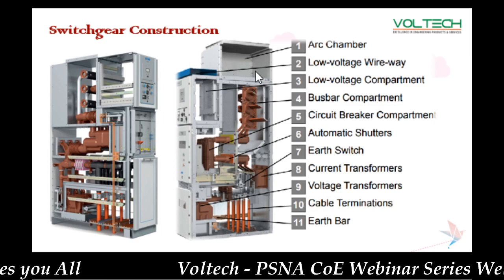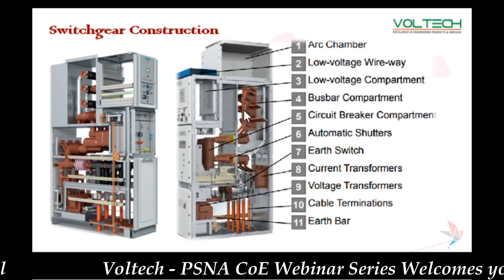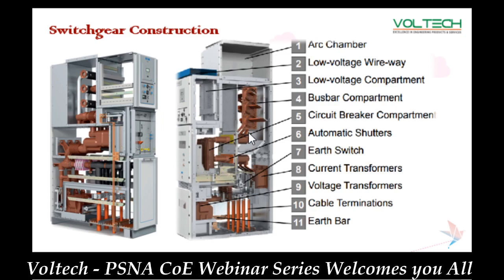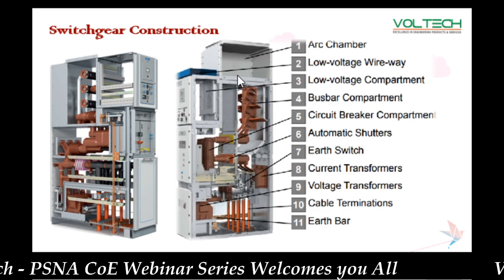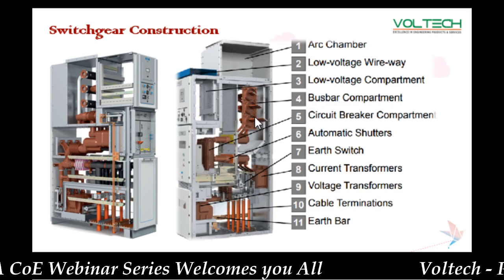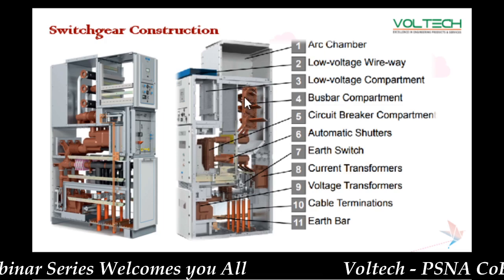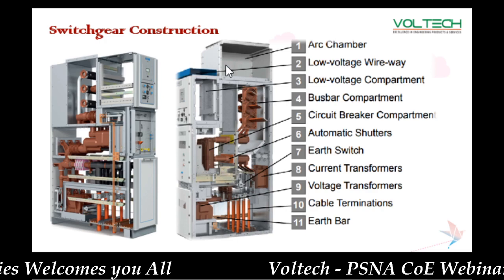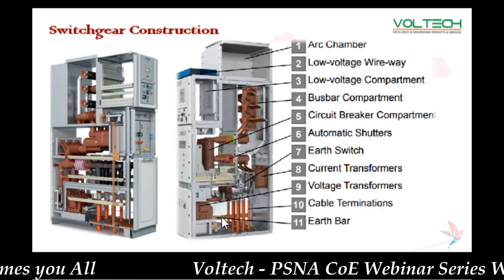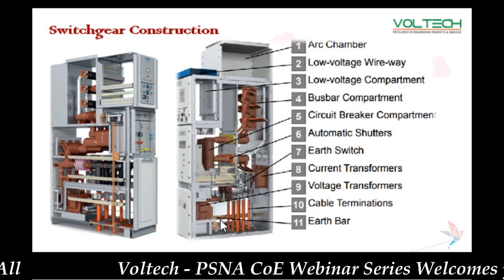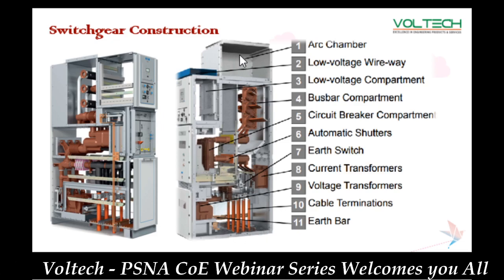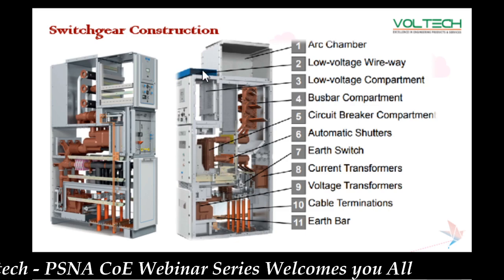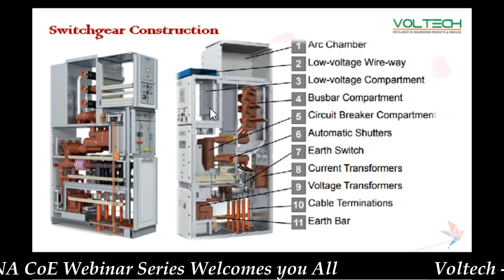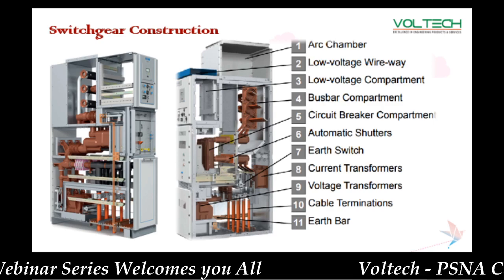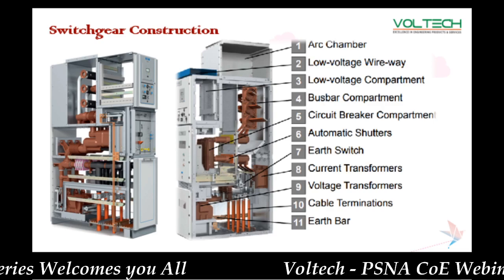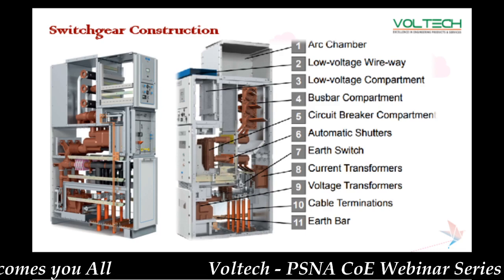So here is one more panel, this is called the arc chamber. Whenever a fault or short circuit occurs in the busbar chamber, this chamber is used to evacuate the smoke from these places. So this is called the arc chamber. And here this is the earth switch. So now we are talking about the internal components. This is the low voltage compartment, where the auxiliary voltage for protection and control is 110 or 220 VDC.